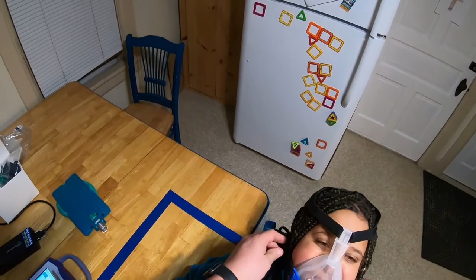The other method that you can do is put it on a test lung. So you'll click non-invasive mode, you'll hit ventilate, you'll have it on the test lung. The apneic period default is automatically defaulted to 20 seconds. And so as long as you poke the test lung less than every 20 seconds, it will think that the patient is breathing, and then that'll keep it happy that way. So that is an option for switching over. So that way you can get your settings dialed in before you put it onto the patient.